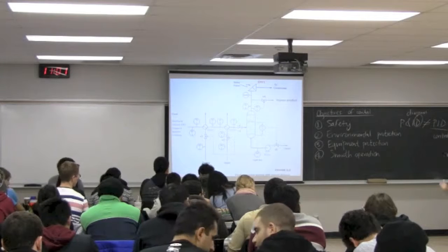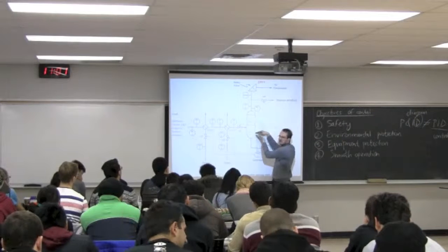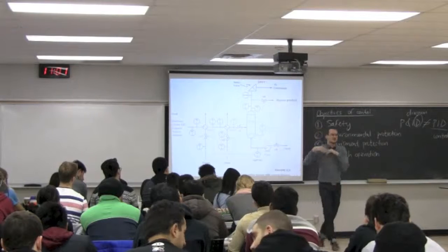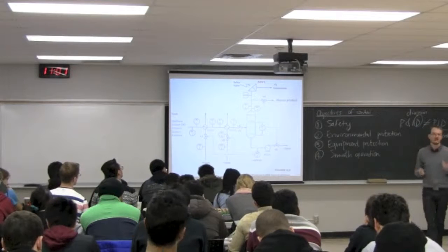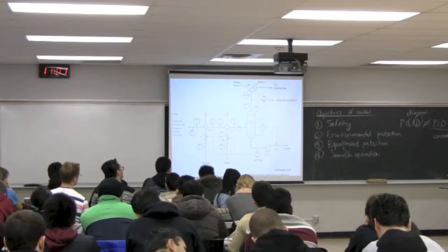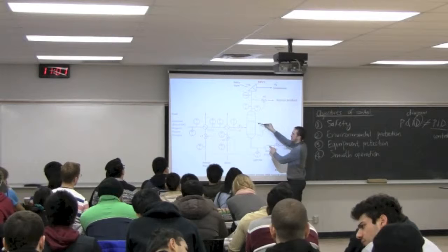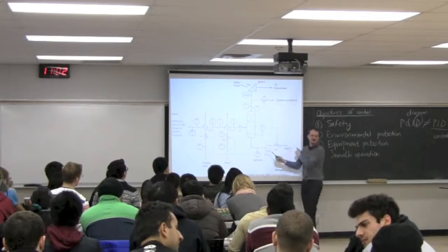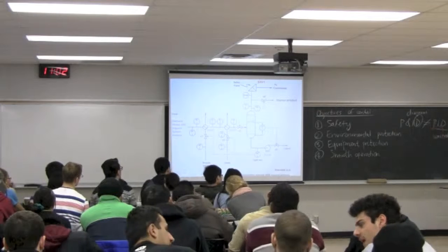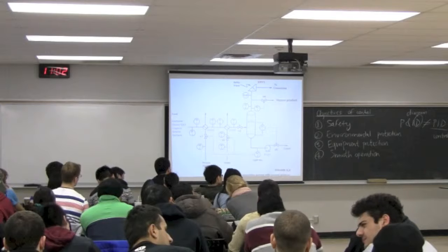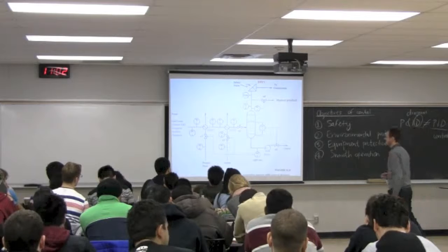Level is another variable that's like that. As long as the level fluctuates, for example, between 5% and 45%, we really don't care. That level can just keep moving anywhere in between. We don't need tight control. So that's a term that we're going to hear later on: tight control or careful control. So smooth operation simply says that if this level is starting to go out of bounds, we don't suddenly open that valve or suddenly close it. We just gradually open it a little bit more and allow the system to slowly move back to where it needs to be. Same as when you're driving a car. You don't suddenly accelerate or decelerate, so that you have a smooth operation of the vehicle.